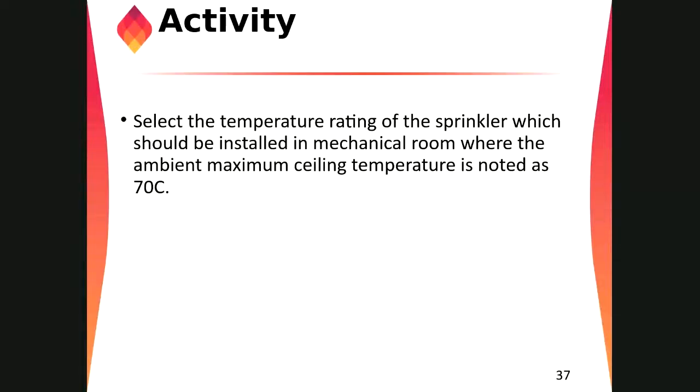So we have one activity here, right? Suppose you are designing a sprinkler system for some mechanical room or some area where there is no HVAC unit, no air conditioning system. The temperature is around 70 degrees Celsius in that room, the ceiling temperature. So what should be the temperature rating of the sprinkler?